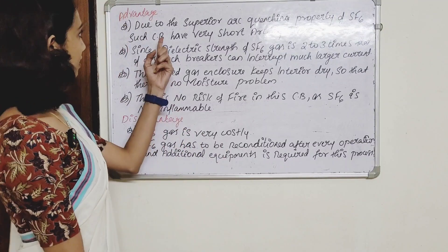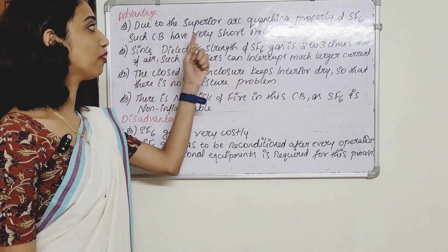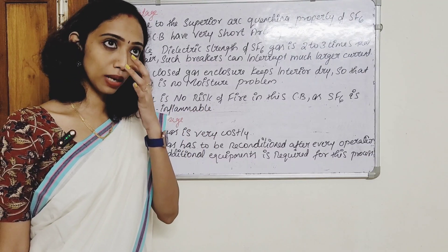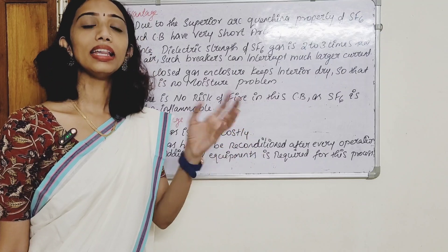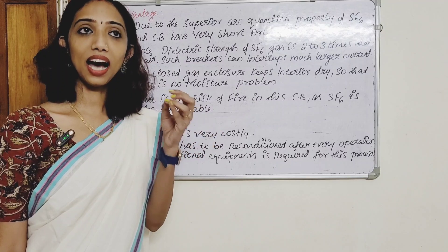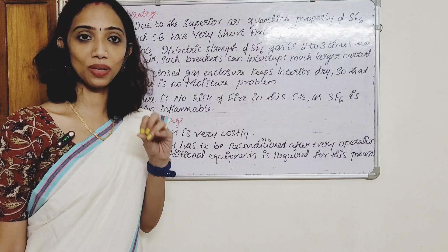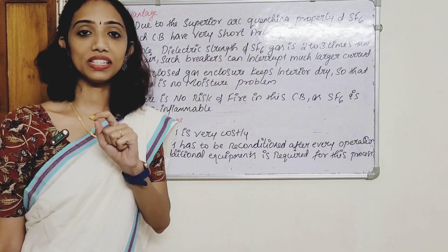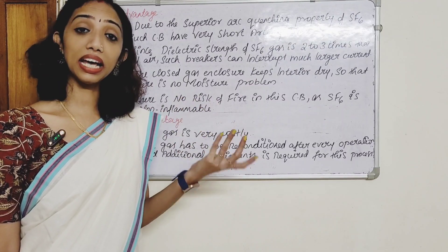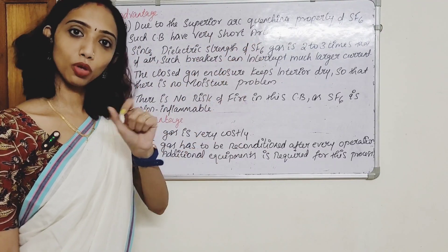The advantage is that due to the superior arc-quenching property of SF6, such breakers have very short arcing time. The high-pressure SF6 flow rapidly captures free electrons to form negative immobile ions, building high dielectric strength to extinguish the arc quickly.